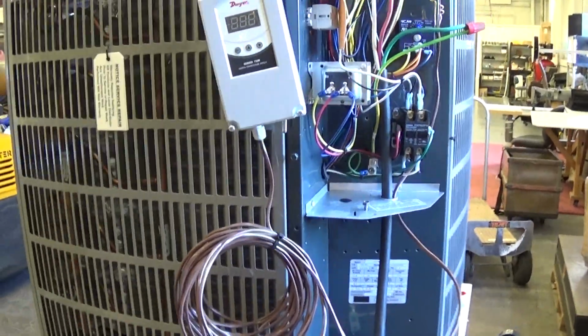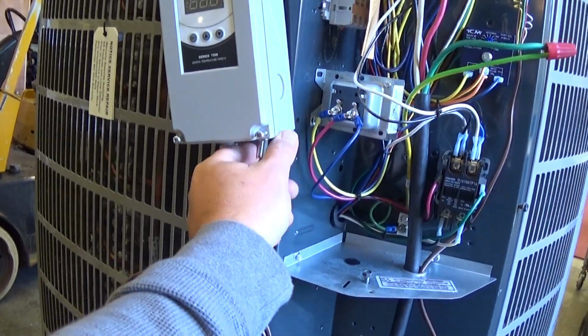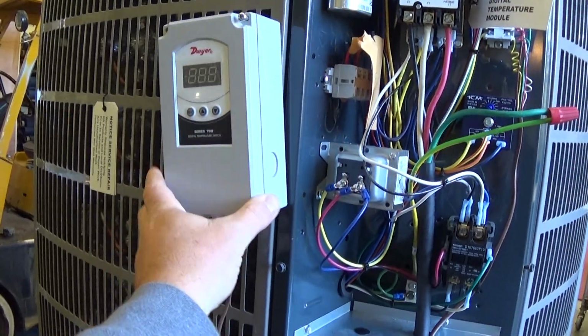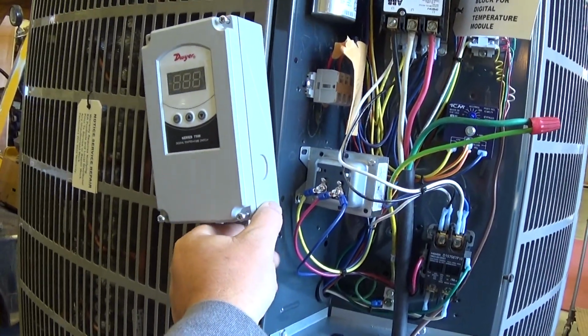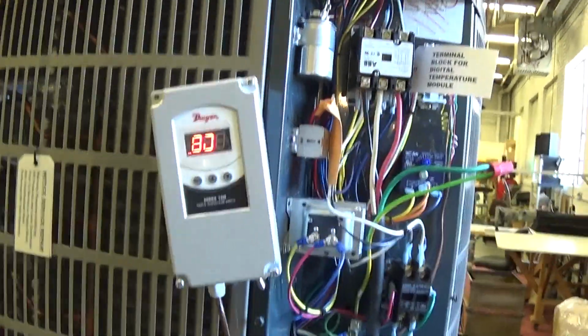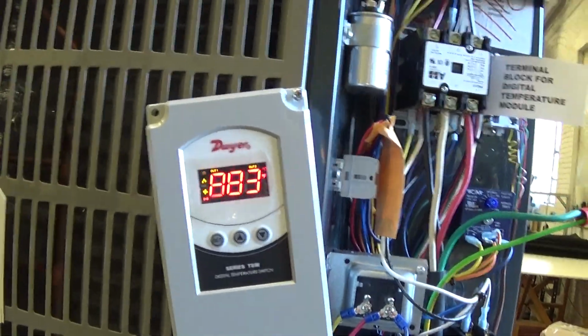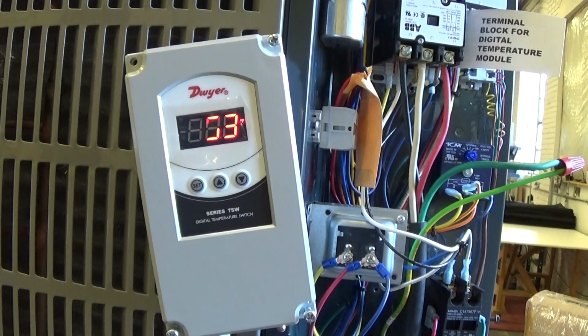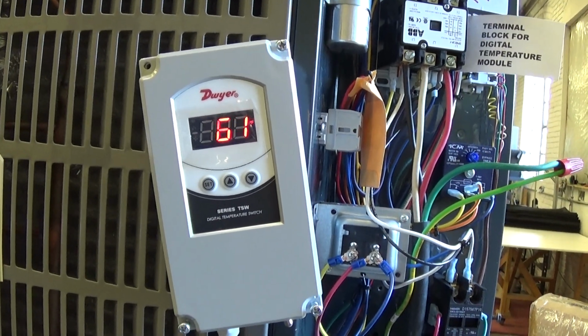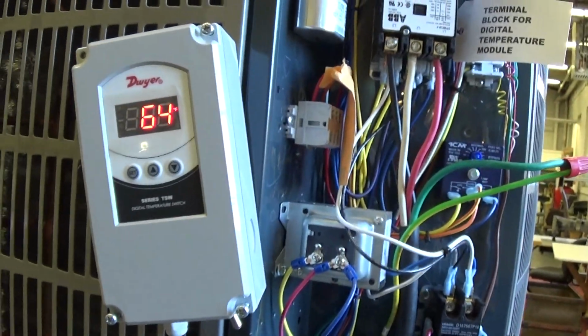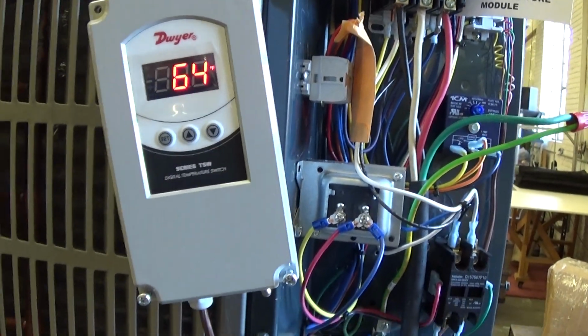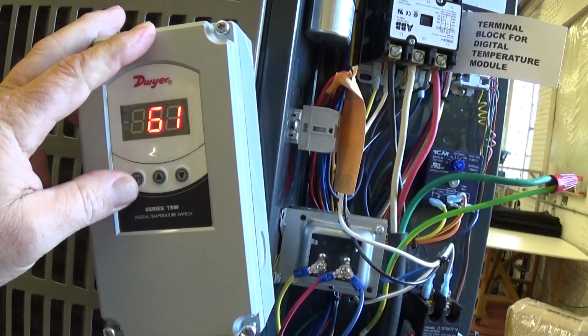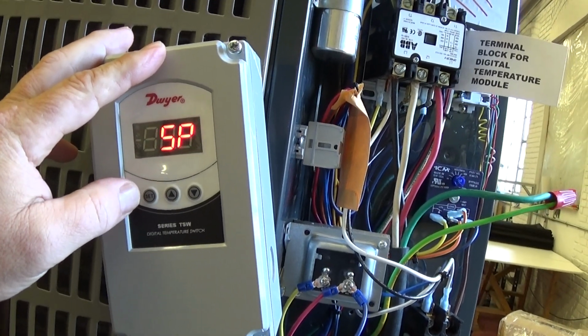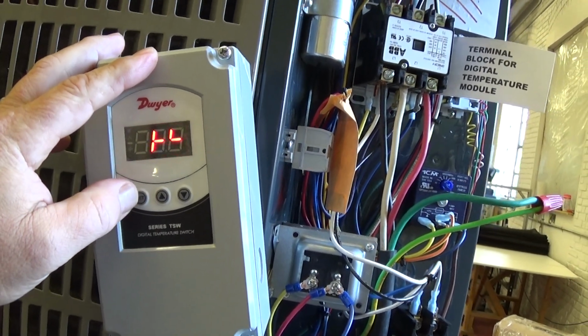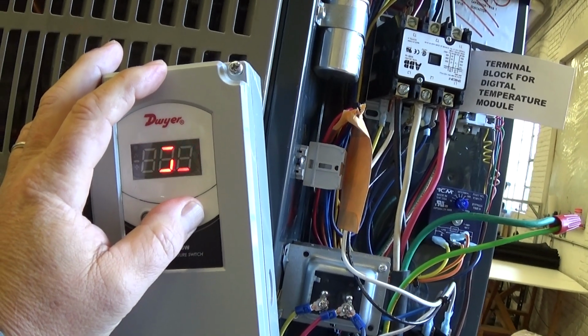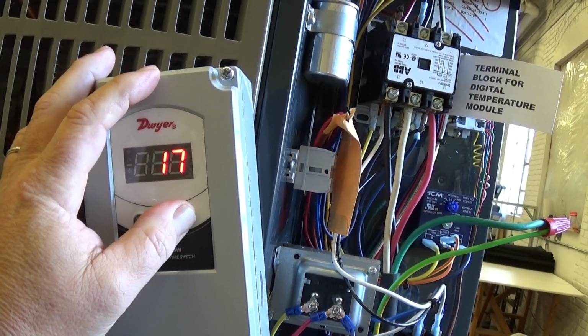So this unit we have been testing for a while. We're going to simply turn the toggle switch on. We just have it hanging on the side of the condenser here. The pump turns on immediately, and the Dwyer controller does a little self-test here. So to change the set point, which we have set kind of high right now, you just simply press, you don't hold, you press set once, SP comes up, press it again, then it tells you what it's set at, and then we're going to bring it down to 25.